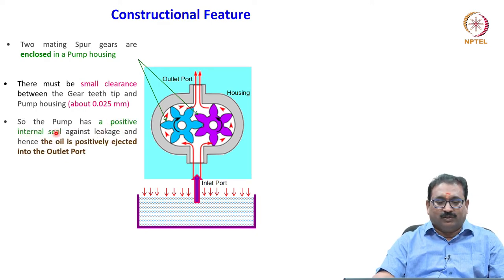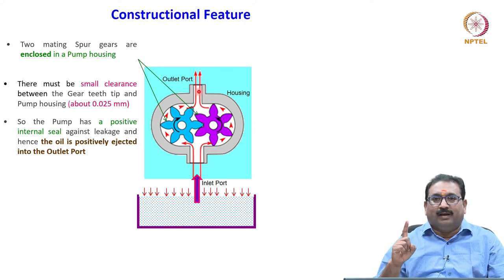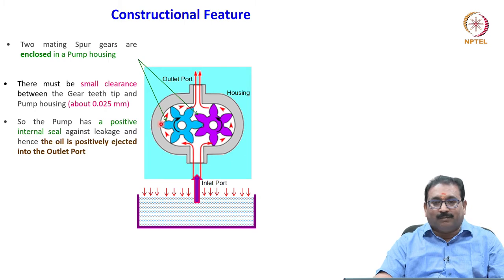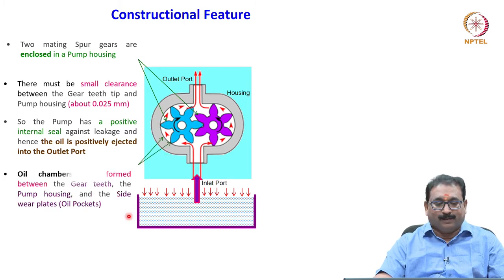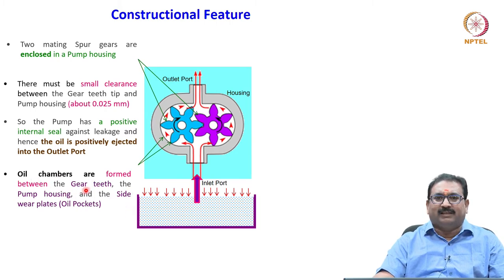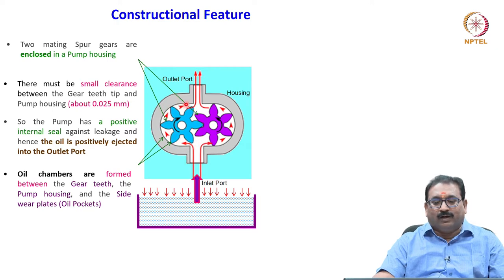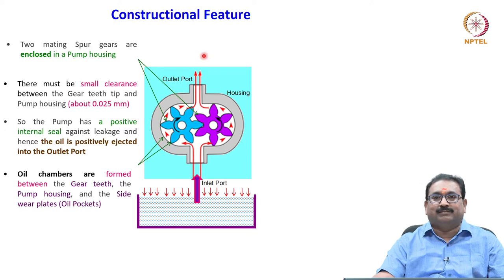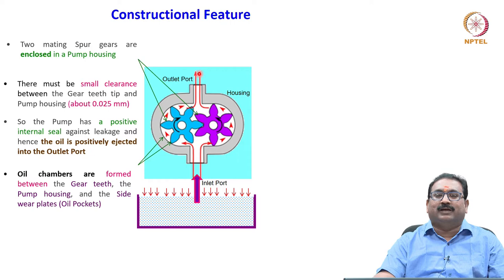The pump has a positive internal seal, hence the oil is positively ejected into the outlet. In hydrostatic pumps, the outlet and inlet are completely separated — only a small gap exists between them. Oil chambers are formed between the gear teeth, the pump housing, and the side wear plates — these are oil pockets. Once oil is caught here, it transports the fluid at the outlet along the periphery. Half revolution, oil is sucked; another half revolution, it is positively ejected because of the internal seals.